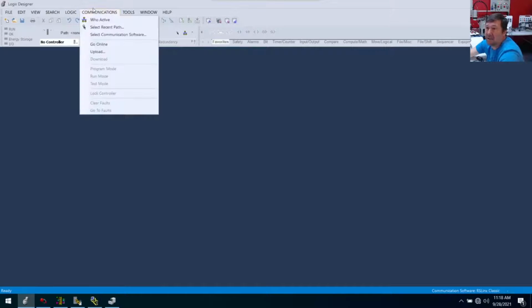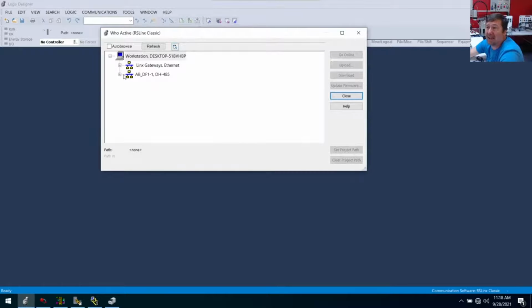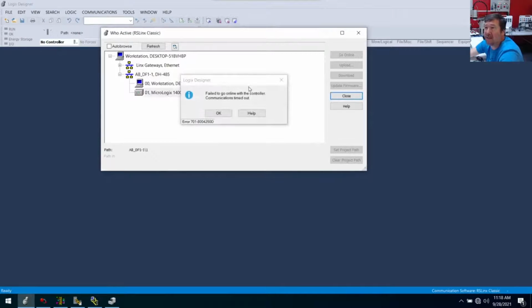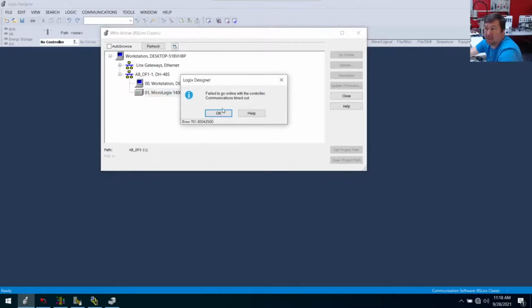All right, now I'm going to go to communications. And notice we do have go online, upload, and we could have download here. I always like to go to the Who Active, and the reason for that is I can make sure that I have the right PLC. All right, we click serial, and there is our MicroLogix. And it says failed to go online with controller, communications timed out, which is going to sound like we have an issue with our communications. And just for insanity, we would probably do it a couple more times. So we would click here, and then maybe we click back here, and we're going to get it again.